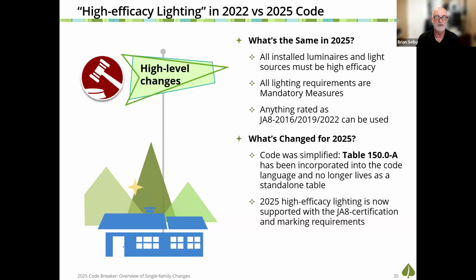Those are referring to the sticker or certification stickers on our luminaires and lamps. What has changed? The code was simplified, meaning that there was a lot of information located on tables to identify whether the luminaires are high efficacy or not. That has just been incorporated into code language. So we've removed the Table 150.0-A. Also, for 2025, high efficacy lighting is now supported with those JA8 certification stickers and markings.